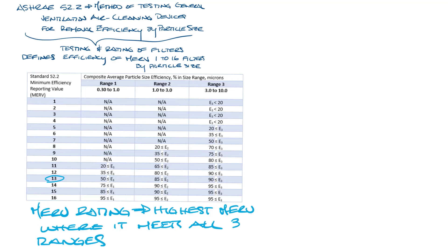The MERV rating of a filter is the highest MERV number where it meets all the requirements for each range. For instance, a MERV 13 filter has to be at least 50% efficient in range 1, 85% efficient in range 2, and 90% efficient in range 3. This allows you to choose a filter based upon the particular contaminant you want to remove.